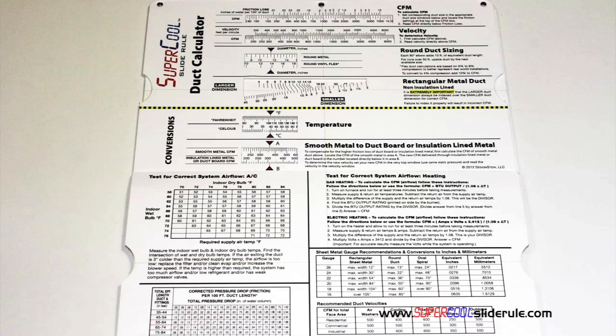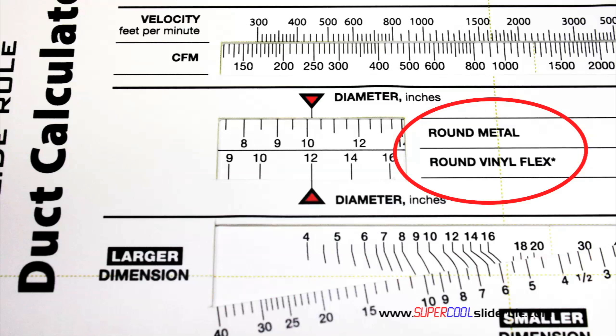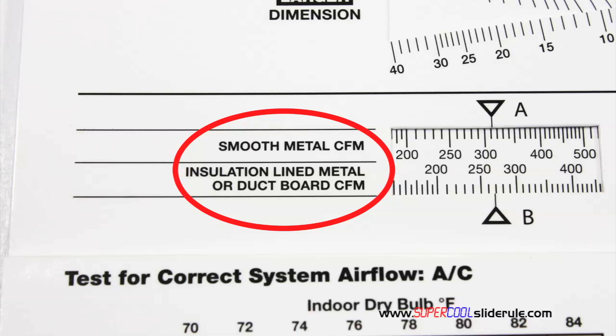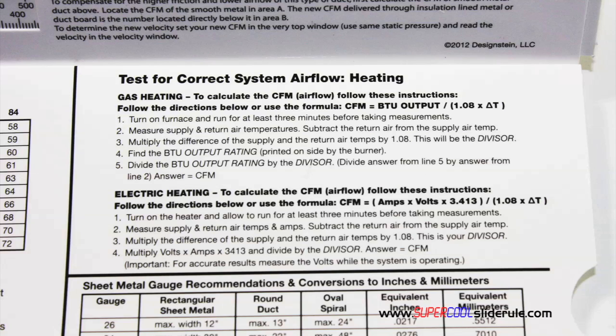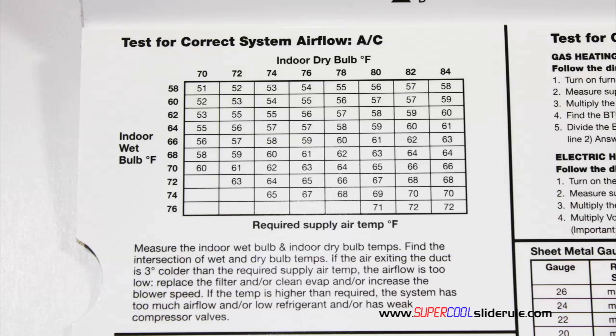Inside, it is packed with even more information. It performs sizing of both metal and flexible duct, and has the only direct reading conversion from smooth metal to insulation lined metal we've ever seen. The majority of technicians have never been taught that if the insulation is on the inside of the ductwork, you cannot size it with a regular duct calculator. It also has step-by-step directions for determining airflow through a gas furnace, electric furnace, or an air conditioning unit.